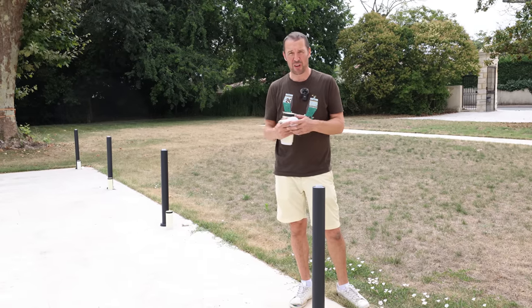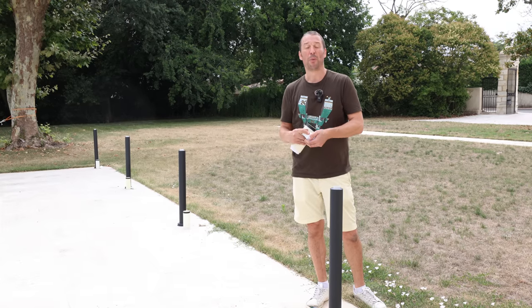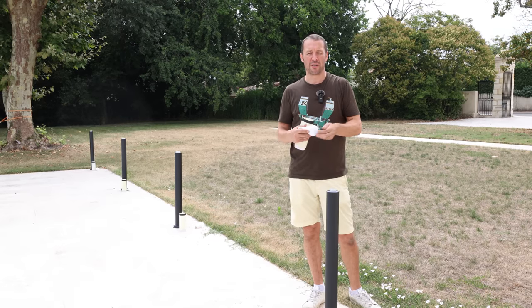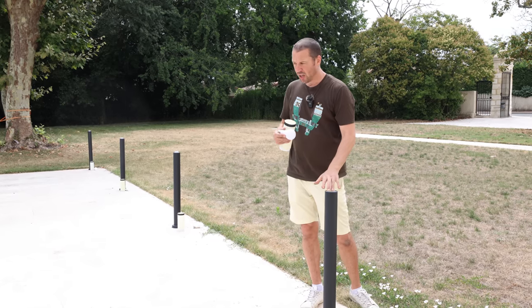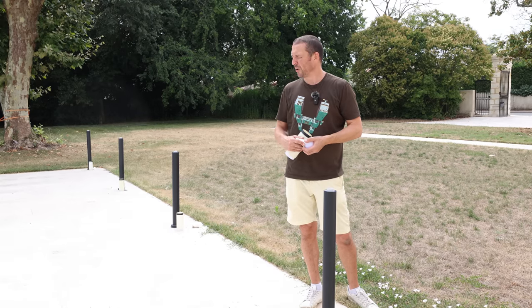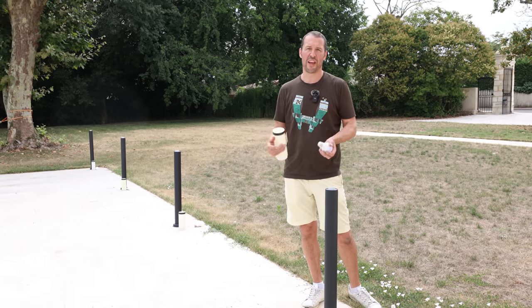That's all that the Consuel found. Of course, they were very important problems, because you wouldn't have that breaker for no reason, and of course you don't want 230 volts around a pool. So yeah, very important things, very small things, and thankfully so quick to fix.